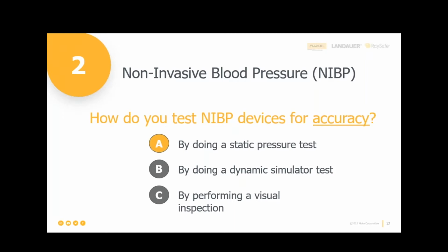Speak up, please. In most instances, they take a reading with the monitor and say, well, I didn't like that reading, so I did it manually, and it's lower. Usually, I'll go through the things and make sure they had the right cuff size. I may even test to make sure there aren't any leaks. Good, all good. Keep going. Then for some of them, if they're pretty consistent, I will explain there's an algorithm doing it in steps, and doing it by listening and slowly deflating is going to be different than the machine stepping it down, and that's going to cause some differences. It absolutely will, and here's why.